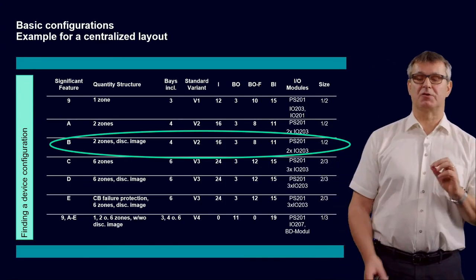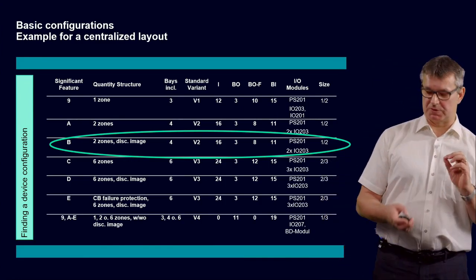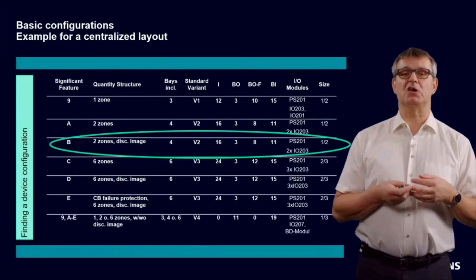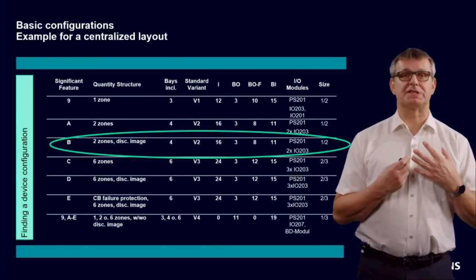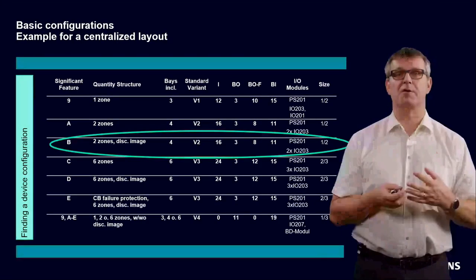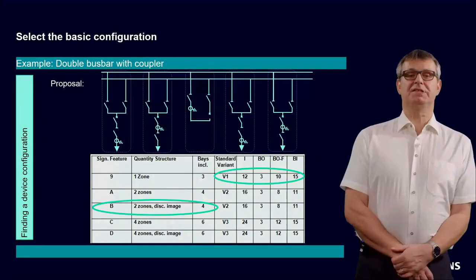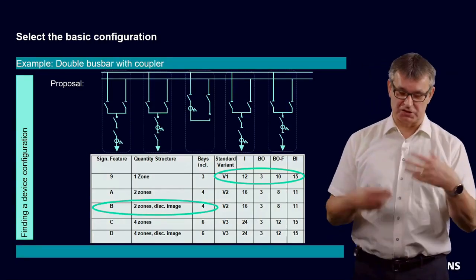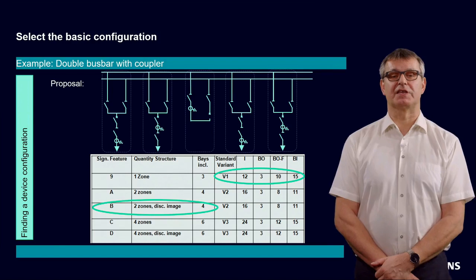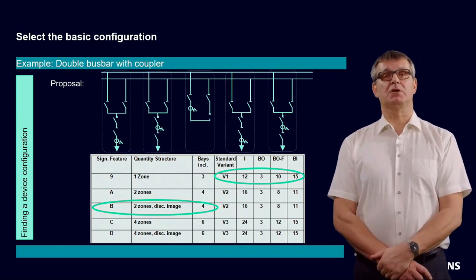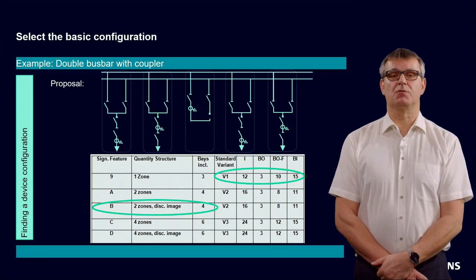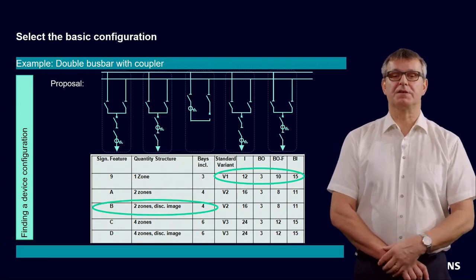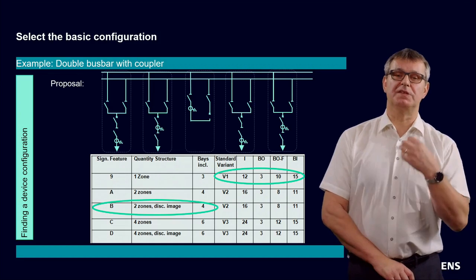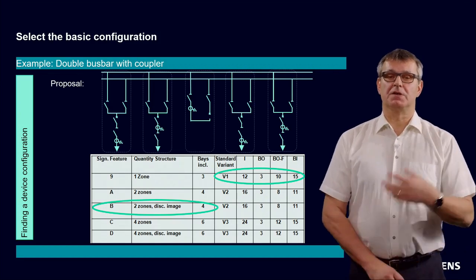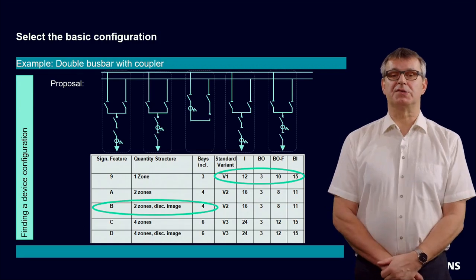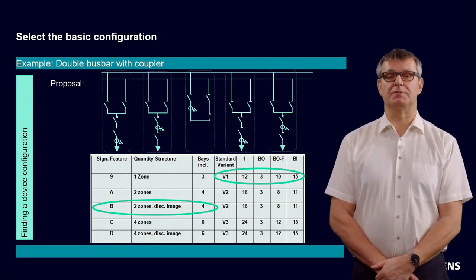outputs. But to make it also obvious that it's only a proposal, you can start also with the standard hardware variant version 1. And we will do this in this case. We will start with significant feature B. We will select a 7SS85 with significant feature B. And we will start our configuration with a hardware variant version 1, which brings us 12 current inputs, which means 3 measuring points, all in all 13 binary outputs and 15 binary inputs.